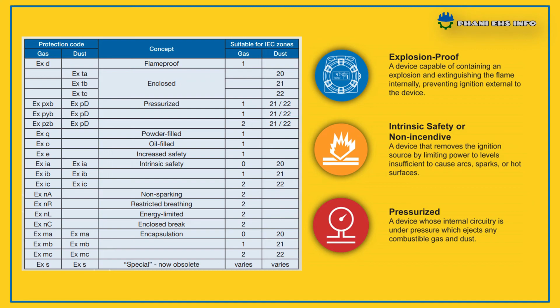Where the equipment contains electrical circuitry, there are a number of ways to prevent sparks, heat or short circuit from causing ignition of the explosive atmosphere. Filling the enclosure with a material which acts as a barrier, a powder, liquid, solid or pressurized inert gas, or reducing the energy, which means intrinsic safety. This classification is shown in this table.